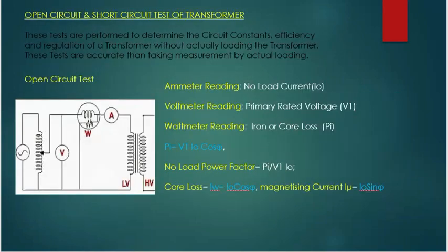So now we will discuss the open circuit and short circuit tests of a transformer. These tests are performed to determine the circuit constants, efficiency and regulation of a transformer without actually loading the transformer. And these tests are more accurate than taking measurements by actual loading, as the power consumption during these tests is very low.